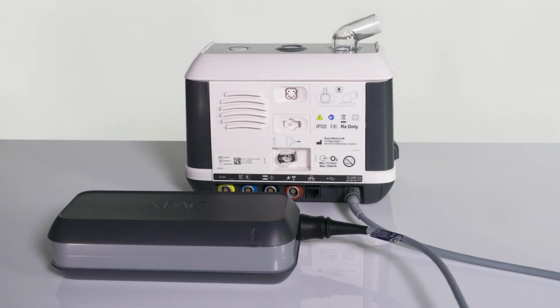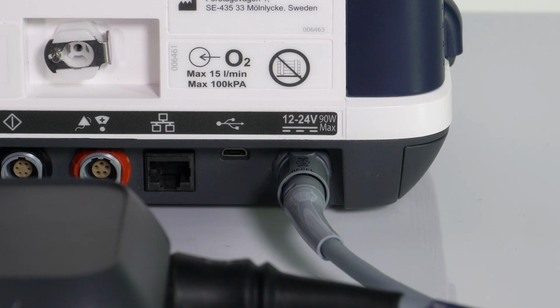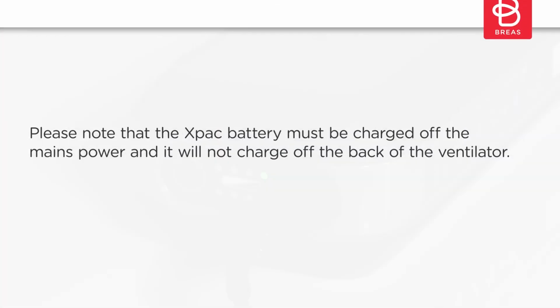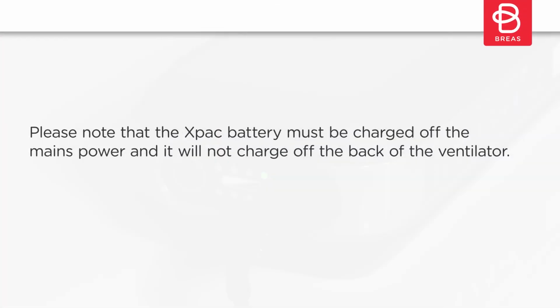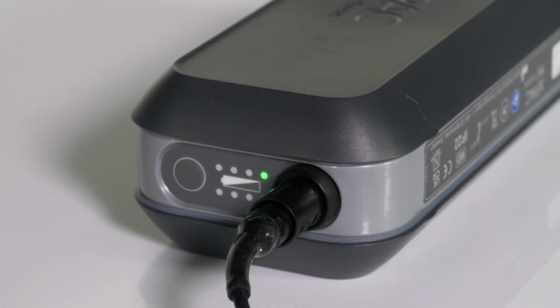It's important to know if it's a single or dual cell Xpac battery you are using, so you can know what backup time to expect. Please note that the Xpac battery must be charged off the mains power, and it will not charge off the back of the ventilator. It will take about 4 hours to fully charge it from empty.